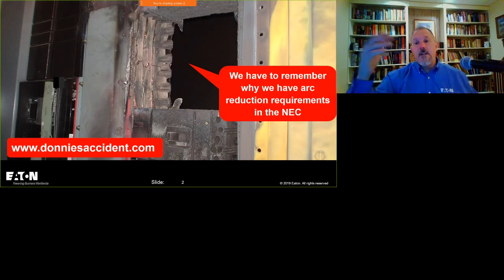Okay, there we go. Secondary network. So this is what Tim was just talking about. When you start paralleling transformers, you're lowering that source impedance, and now you can get higher fault currents. And I've typically seen, like this is 150,000. I know downtown Pittsburgh.